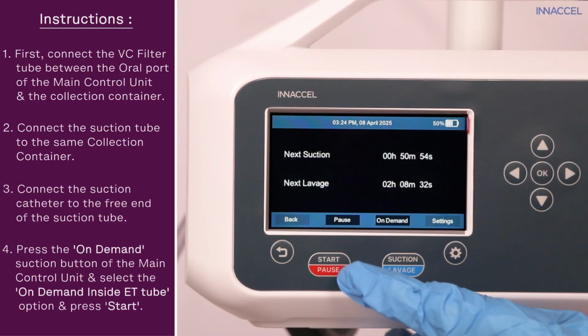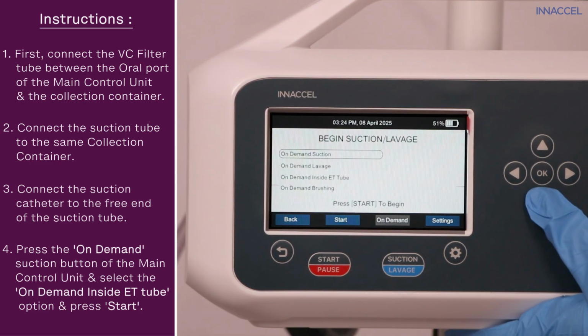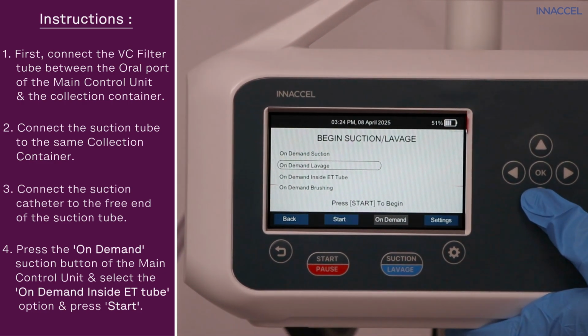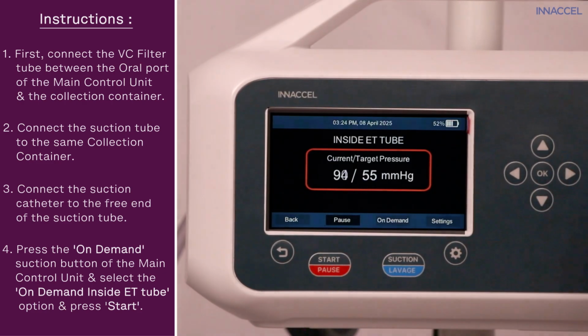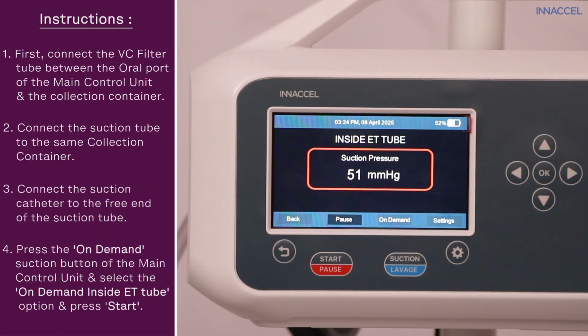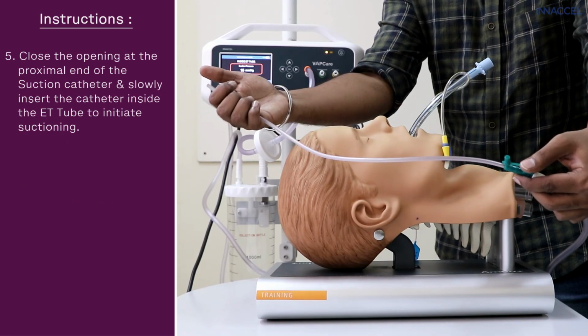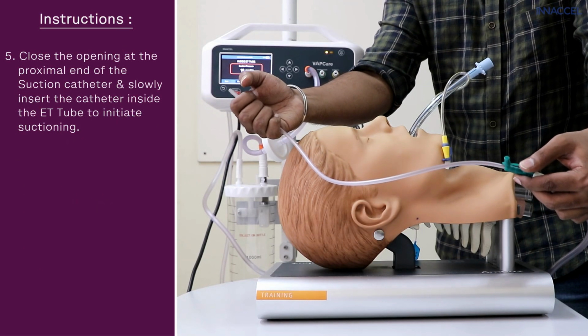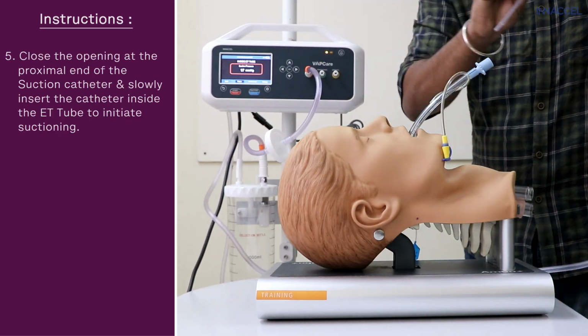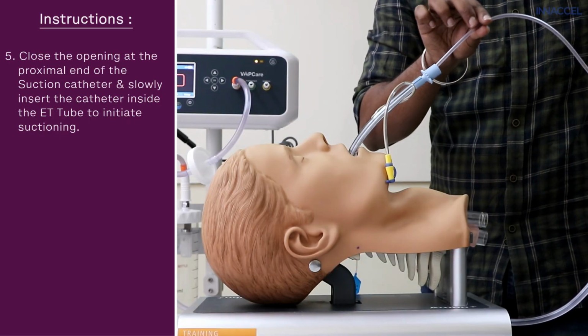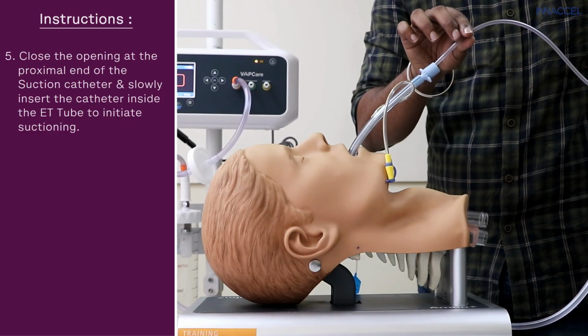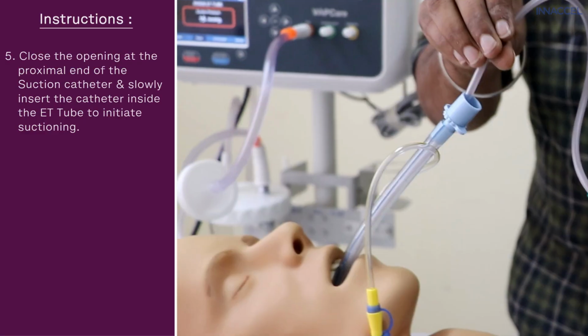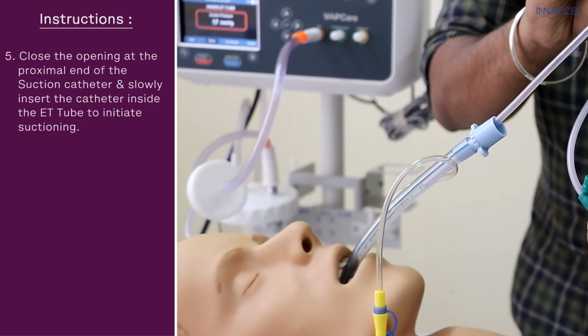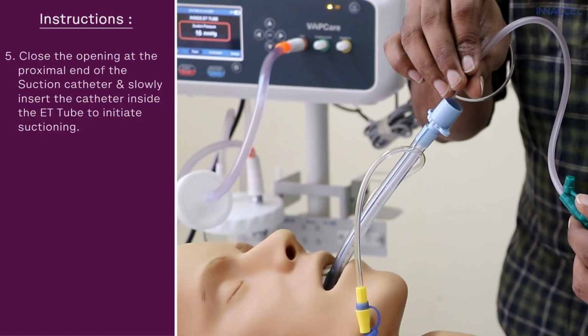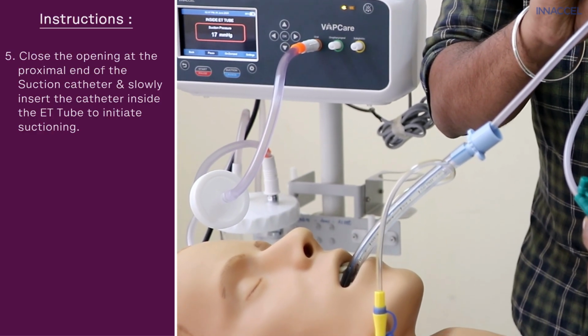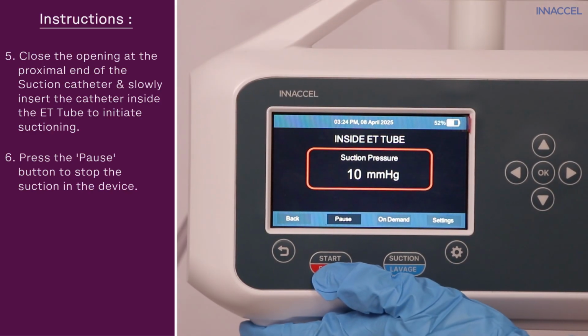Press the On-Demand button of the main control unit and select the On-Demand Inside ET Tube option, and then press Start. Close the opening at the proximal end of the suction catheter, and slowly insert the catheter inside the ET tube to initiate suctioning. Press the pause button to stop the suction in the device.